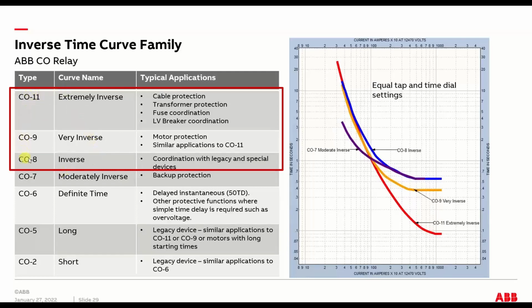And probably in modern days, you really only have to worry about CO11 through CO8, extremely inverse through inverse. The rest of them, except for definite time, the long and the short and moderately, are kind of legacy curves. But you can see that as the curve type changes, its response changes. A CO11, with its inverseness, so to speak, gives it more of an I squared T response, and then a very inverse is a little bit less than an I squared T and more of a thermal overload type response. So these are usually the basic selections you have for curves when you're doing the protective coordination study.